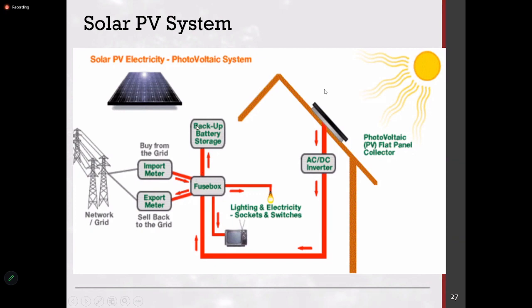The other way out is to use a battery backup storage, where you put your extra into the battery pack, and if you still have more extra, then you can export. You put it into the battery pack, and when you want it, you take it from the battery pack. But the issue is that charging and discharging the battery has about a 20% loss.